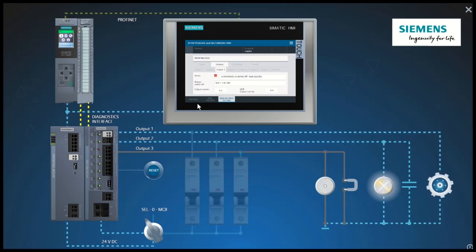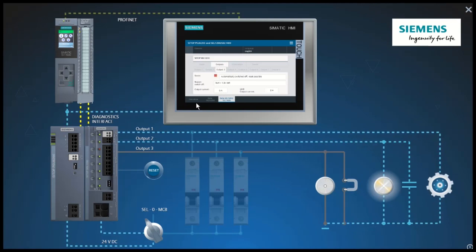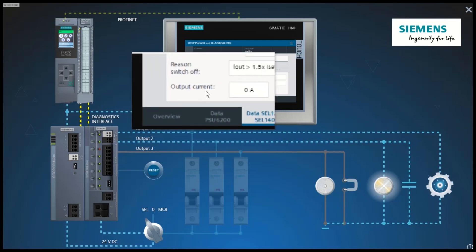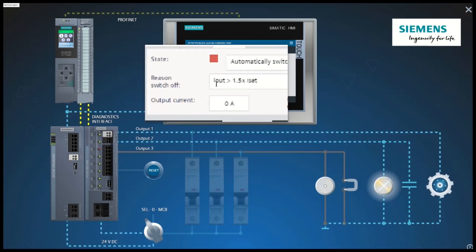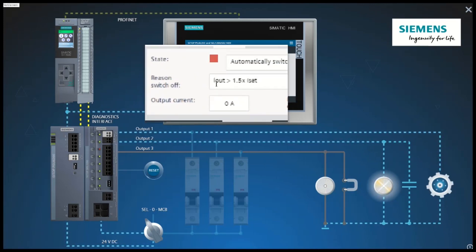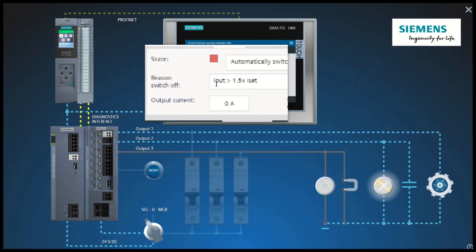The faceplate shows the reason for the shutdown. The output current was at least 1.5 times higher than the set current. So the user knows that a very large overload is involved.